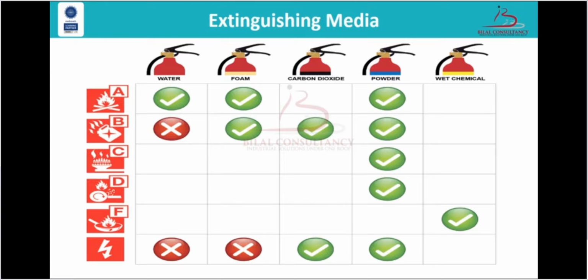Just keep in mind that dry powder fire extinguishers are not suggested for use on any kind of electrical equipment because they contain powder, and during the extinguishing they can extinguish the electrical fires, but they will damage the electrical equipment because of the powder being used. That powder will stick on the electrical equipment circuit, and the maintenance and repairing of that circuit will be very much difficult after the fire.